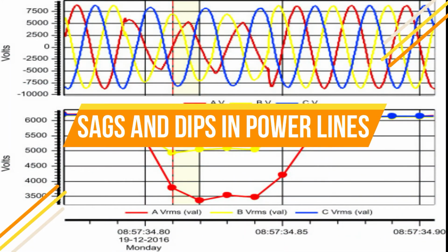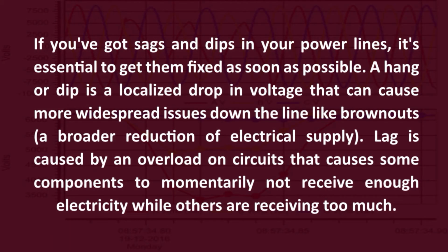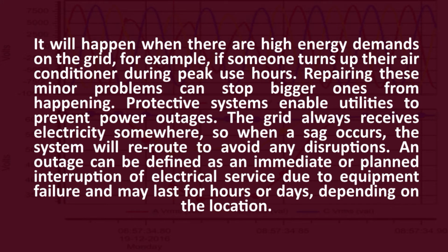Sags and dips in power lines. If you've got sags and dips in your power lines, it's essential to get them fixed as soon as possible. A sag or dip is a localized drop in voltage that can cause more widespread issues down the line, like brownouts, a broader reduction of electrical supply. A sag is caused by an overload on circuits that causes some components to momentarily not receive enough electricity while others are receiving too much. It will happen when there are high energy demands on the grid, for example, if someone turns up their air conditioner during peak use hours.